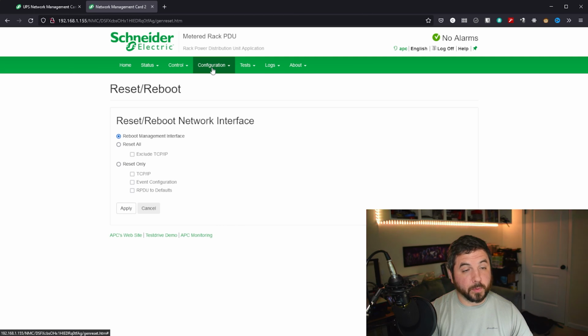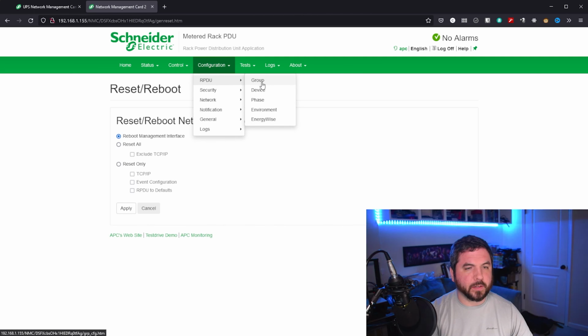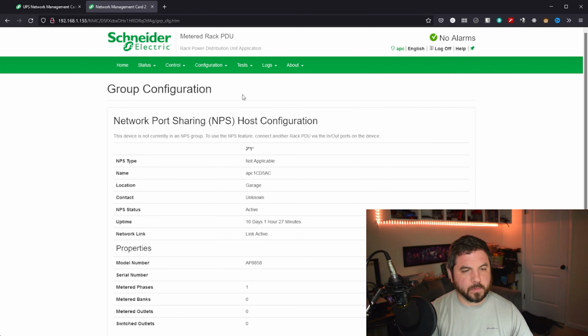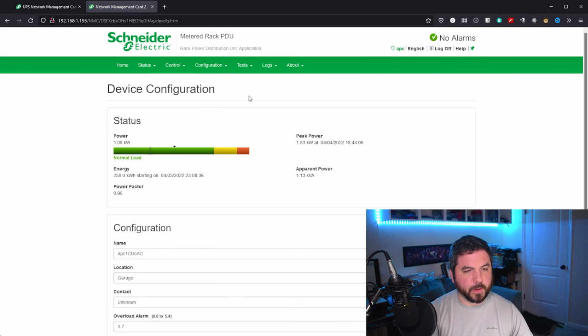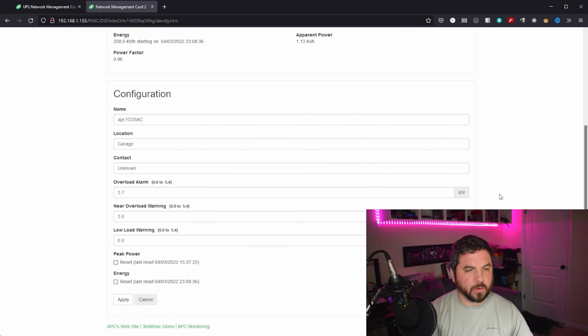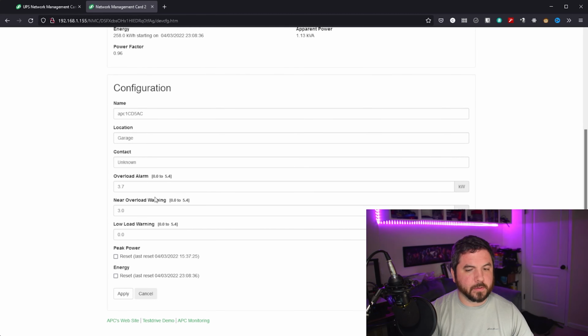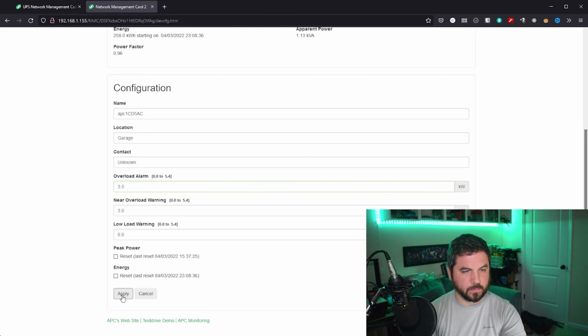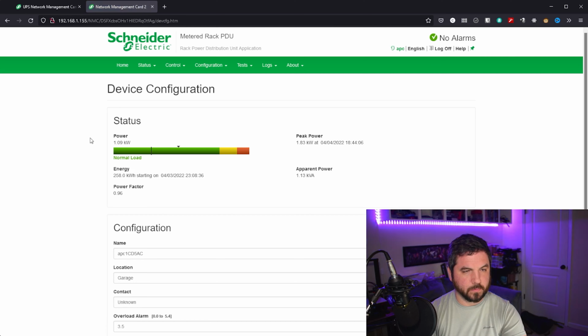It's going to look very similar to the UPS, so we're just going to go through these real quick and point out any differences. This is where you would configure the network port sharing if you had multiple PDUs. And here's more information about the device. You can set the load, alarms, and the warnings. Because the UPS underneath can't go higher than 3,500, we should update that to 35. Yep, and there we go. Now that's within spec of the UPS.